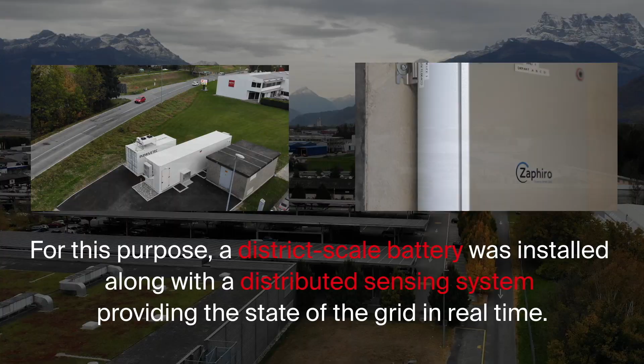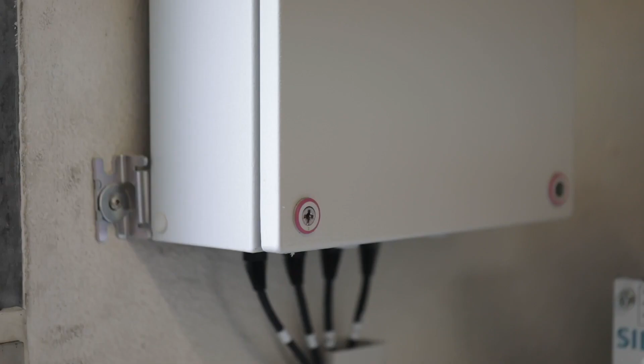The first one is the so-called grid awareness, made possible by distributed sensing using phasor measurement units. At SCCER we developed SynchroGuard, a distributed grid management solution that combines high-speed time-synchronized measurement with our proprietary software platform. Data is sent via public 4G network to our platform, where we process it and extract the state of the grid in EGL, in real time, every 20 milliseconds. The state of the grid means voltages, currents and power flow.